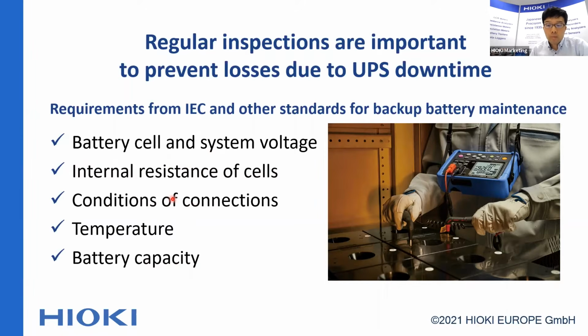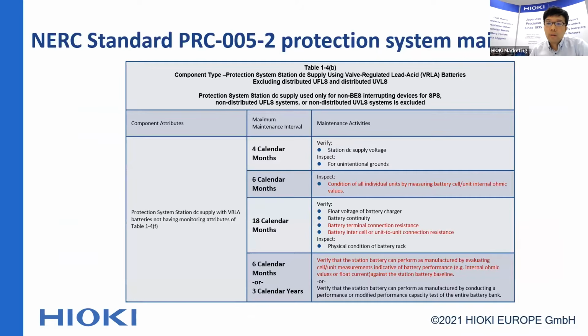So regular inspection is important, but how often should we check the UPS? The NERC shows guidelines for how often we should check the lead acid battery conditions. For example, it says every 6 months, we should inspect the conditions of all individual units.